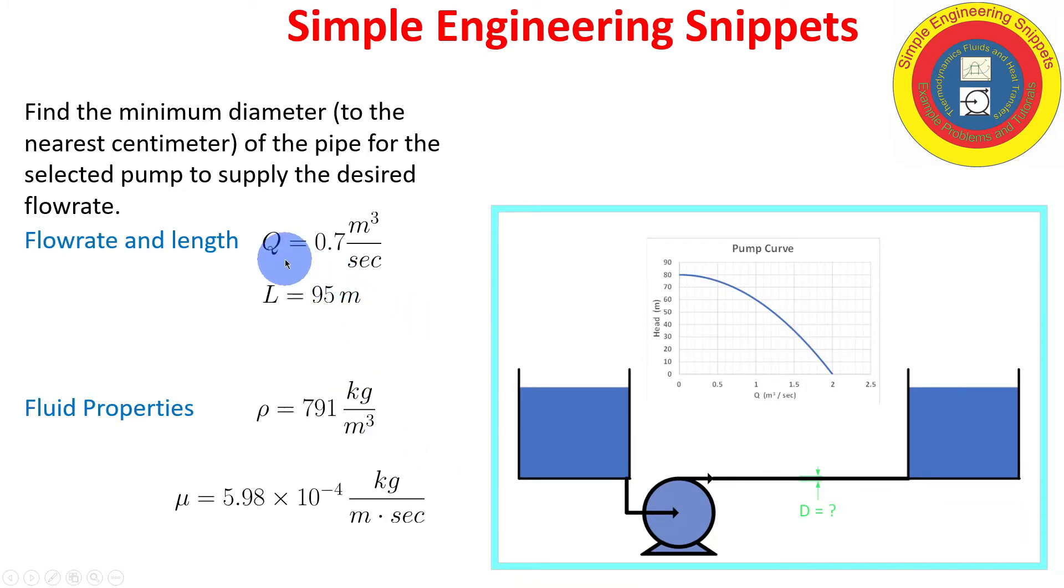We have a lot of data provided including the desired flow rate of 0.7 cubic meters per second. So we hope to size our pipe so we are going to be delivering exactly this flow rate. However, likely we're going to have to slightly exceed that because we are limited to selecting the diameter to the nearest centimeter. So we're not going to be doing 32.634 centimeters. It's either going to be 32 or 33. The length of the pipeline is 95 meters.